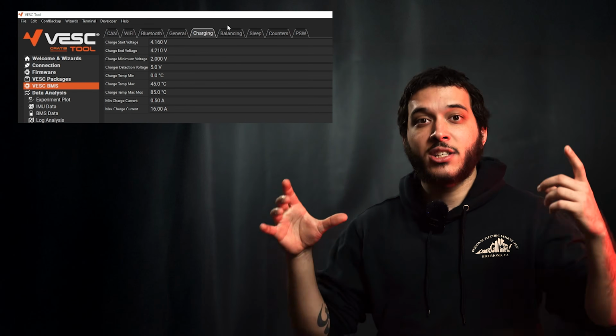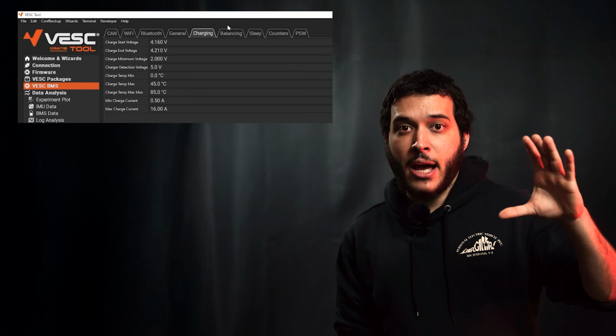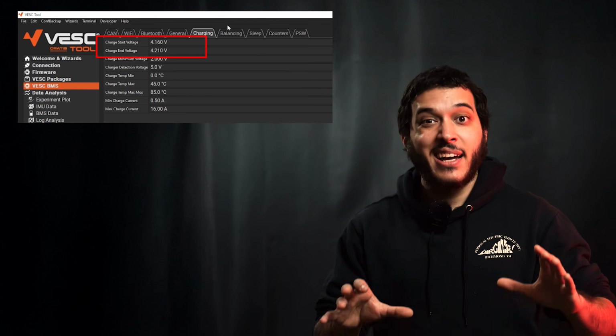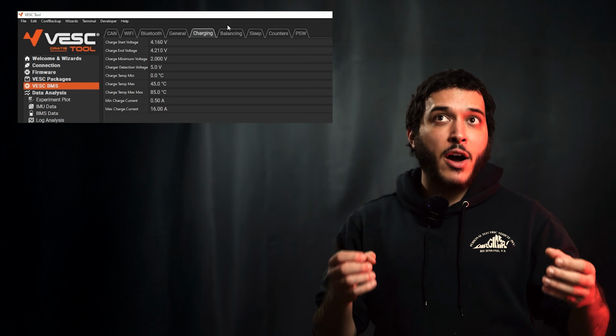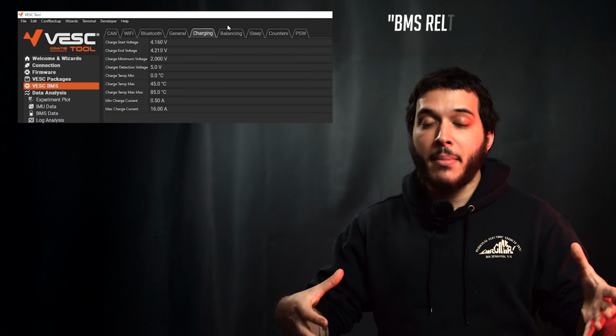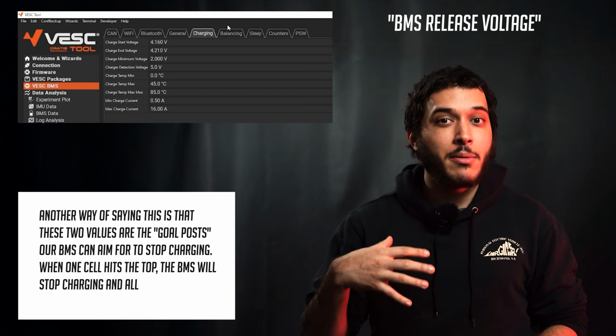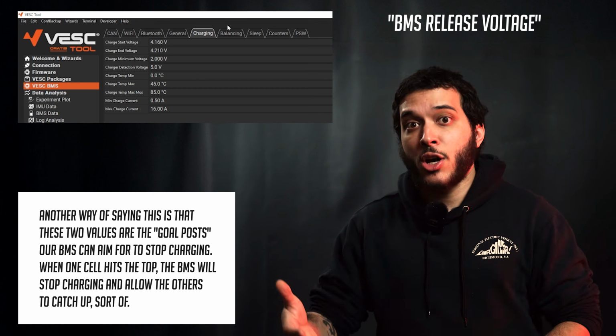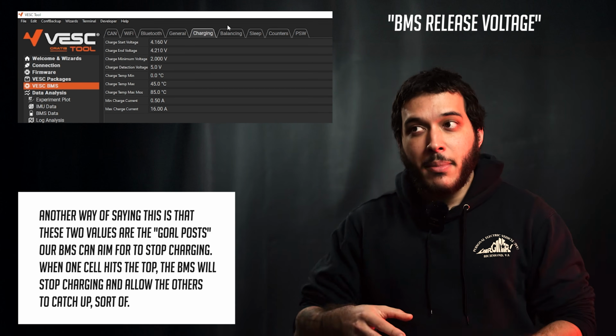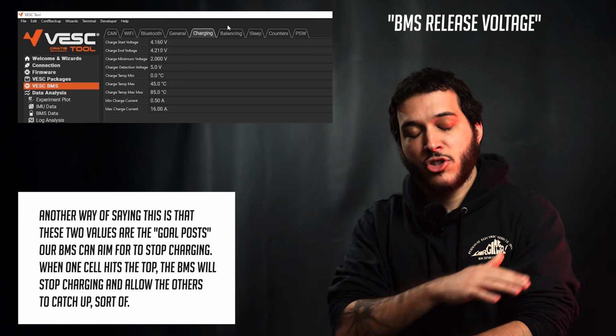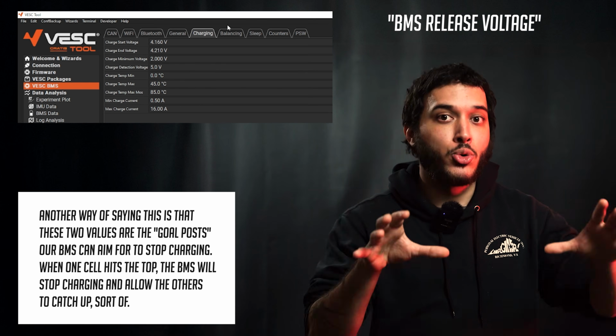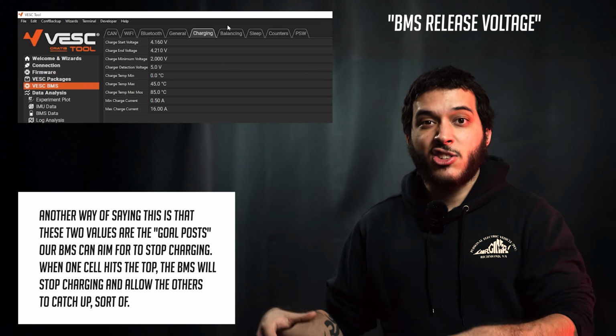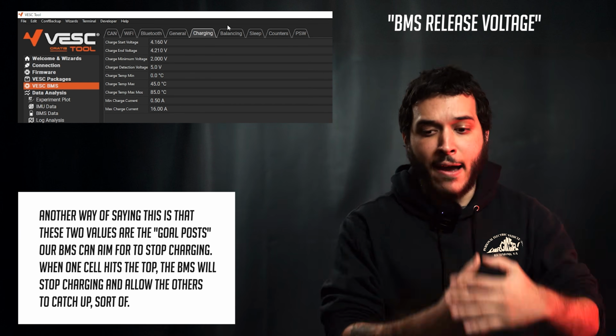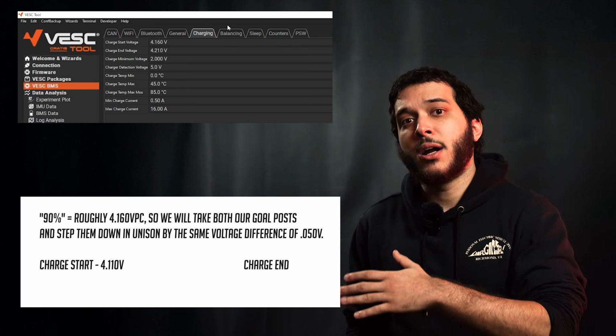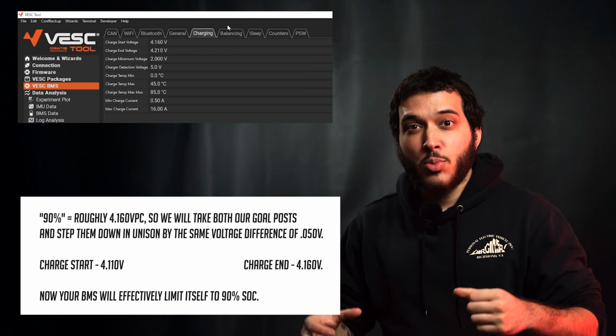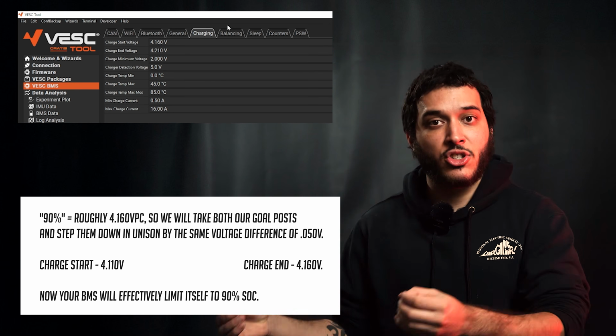To do this, go inside the charging tab. The first two values are charge start voltage and charge end voltage. Both of these are what we'd call the BMS release voltage. This is how the BMS will stop charging if one cell overshoots during a charge. The BMS detects this overshoot and stops charging. By adjusting these two values, we can tell the BMS to limit cell charging to whatever voltage we want. If we want to limit our battery pack to 90%, this would effectively be 4.16 volts.